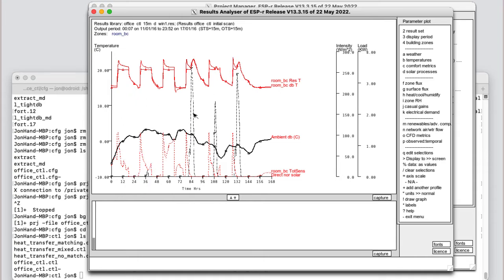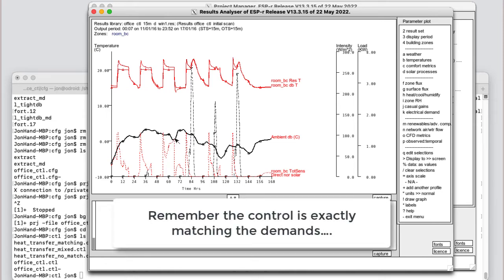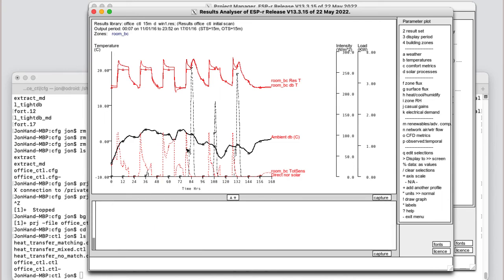There's not much sunlight on these days, and there is sunlight toward the latter part. We can see there's a bump up in temperature after the sunny period. Here's what I would expect in terms of heating. In the morning, it pops up. We're not using 2 kilowatts, we're using something like 1.5. Again, it drops down during the day to maintain the set point, has a brief morning peak. The trick is very brief. And then we've got another peak, and then it starts climbing back up again. On the sunny day, we don't have anything in the latter part of the day. We could probably get by with much less than 2 kilowatts in that room.